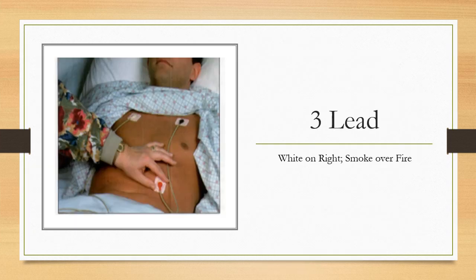For three-lead electrode placement, the mnemonic is 'white on right and smoke over fire.' The white electrode goes on the right shoulder just beneath the clavicle. The black electrode (smoke) goes on the left shoulder beneath the clavicle. The red electrode (fire) sits just beneath the rib cage on the left side of the body.